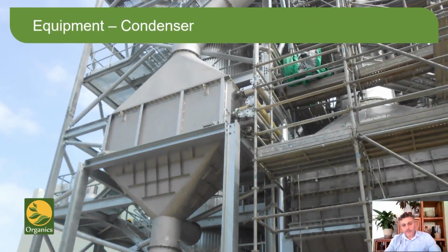The last bespoke heat exchanger we use is the condenser. The condenser is essentially a low temperature economiser, but a lot of the heat that is being recovered is latent rather than sensible. The ammoniated air that leaves the stripper is saturated and hot. By transferring the heat into the incoming leachate, we obviously save energy, but we are also reducing the amount of water being taken through to the thermal destructor.